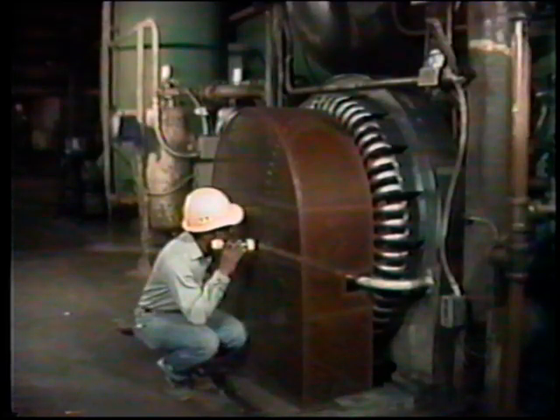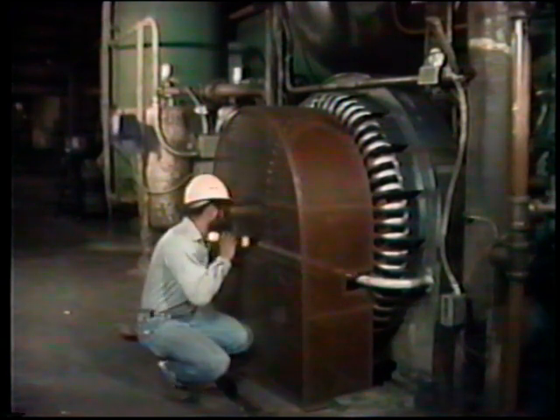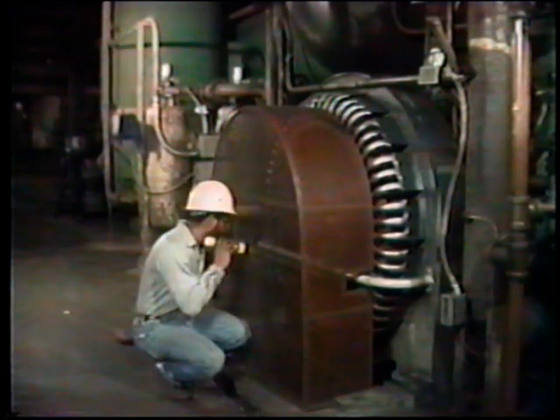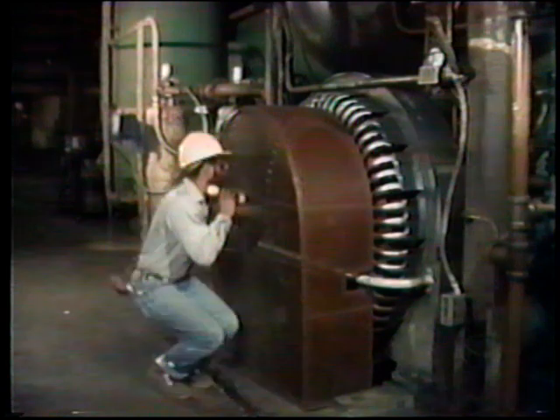Keep all your senses alert for any indication of a motor problem. Always be on guard for any unusual odors. An abnormal smell could be a sign of burnt insulation. Now, to inspect a motor more thoroughly, you're going to need to examine it when it's not operating.